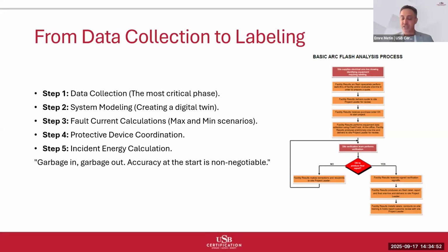Step 5, incident energy calculation. Finally, we calculate the actual thermal energy that would be present at typical working distances. This calculation considers arc currents, durations, distance, and the environmental factors. The process flowchart shown here illustrates the systematic approach required. Notice the verification steps. Quality analysis includes multiple checks to ensure results are reasonable and consistent. The end result is specific incident energy values and arc flash boundaries for every significant location in your electrical system. This transforms abstract hazard awareness into specific, actionable protection requirements.